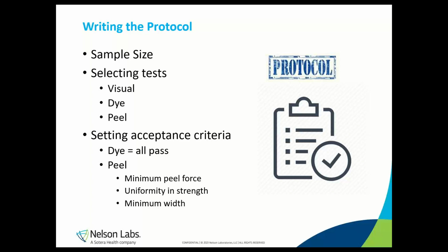In addition to a minimum seal value, you may want to consider a specification around the standard deviation of the peel force. A good sealer should be able to produce a set of seals with a tight standard deviation. If the peel force values are all over the board, it shows that you're making inconsistent seals and your sealer is unreliable, which means that your sterile barrier packages will not be reliable. Remember, the point of the validation is to prove that we can get the same output over and over. So if the seal strength is inconsistent, we aren't meeting the validation objective.